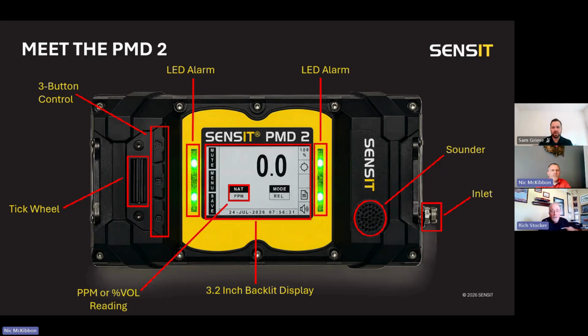You can see over to the left side on the face of the instrument, we do have a tick wheel. So this unit can be used like a SENSIT Gold, the old gas tracker technology of a Geiger counter pinpointer for checking above ground piping. Our LEDs surround the display of the instrument itself. As you can see on the display, we show a PPM reading to start out with, 0.0 PPM. So our first low-level resolution will be 1/10 of a PPM.